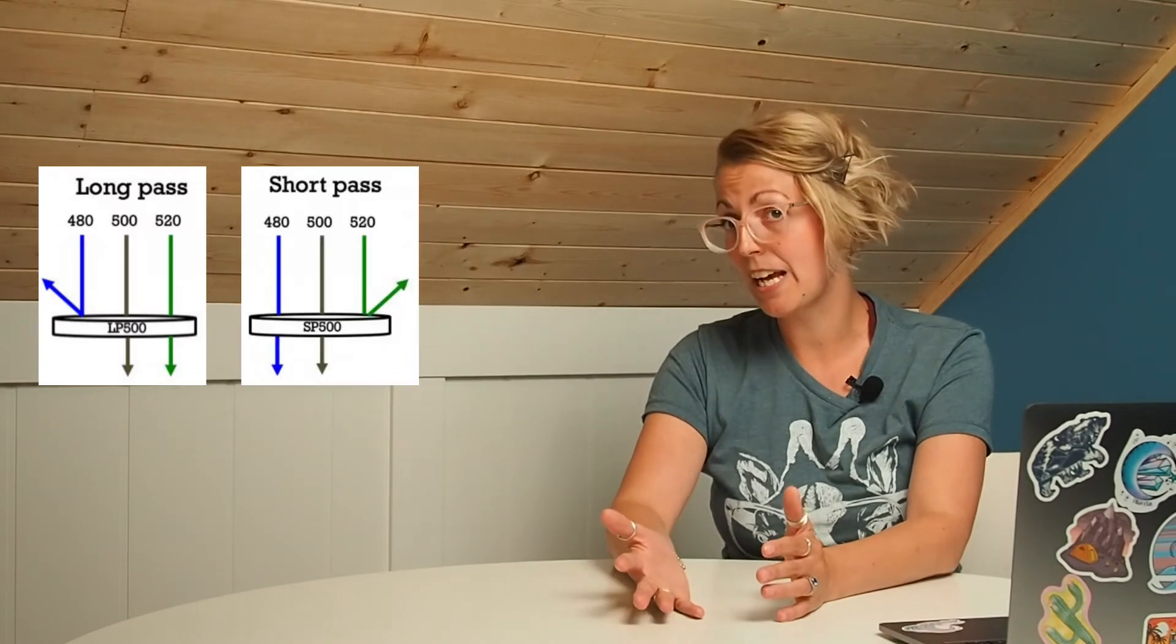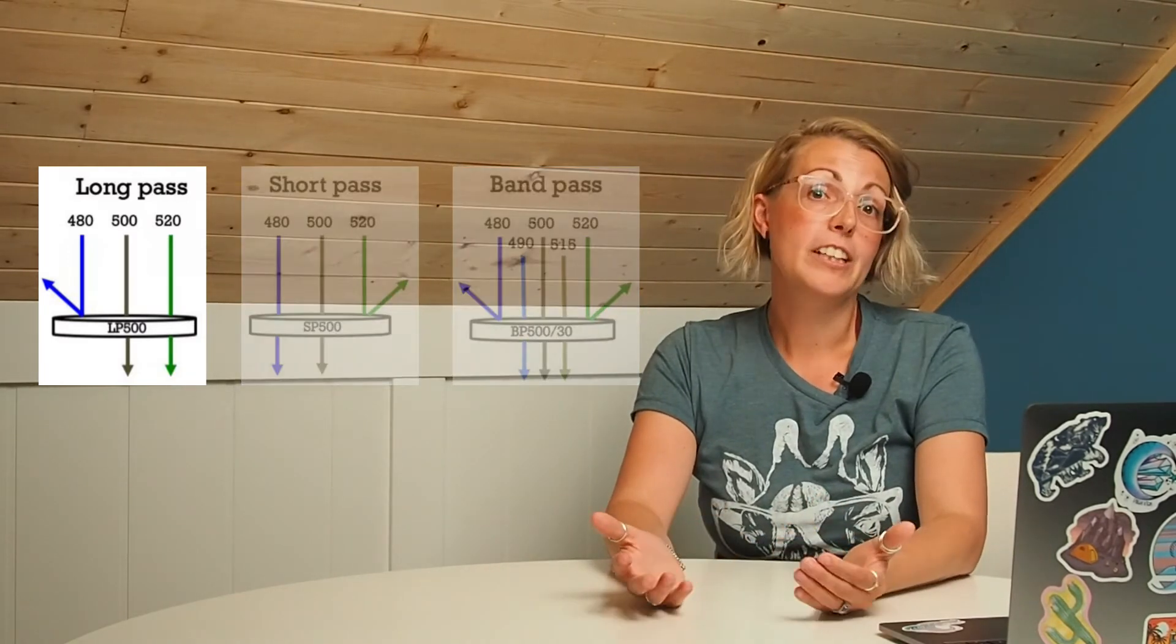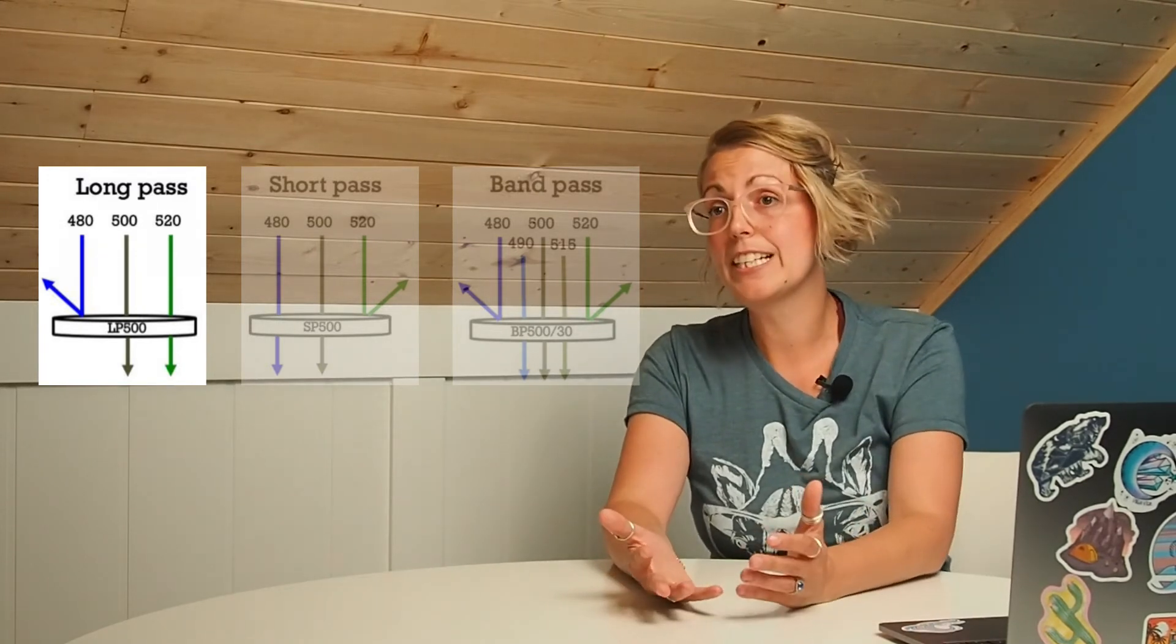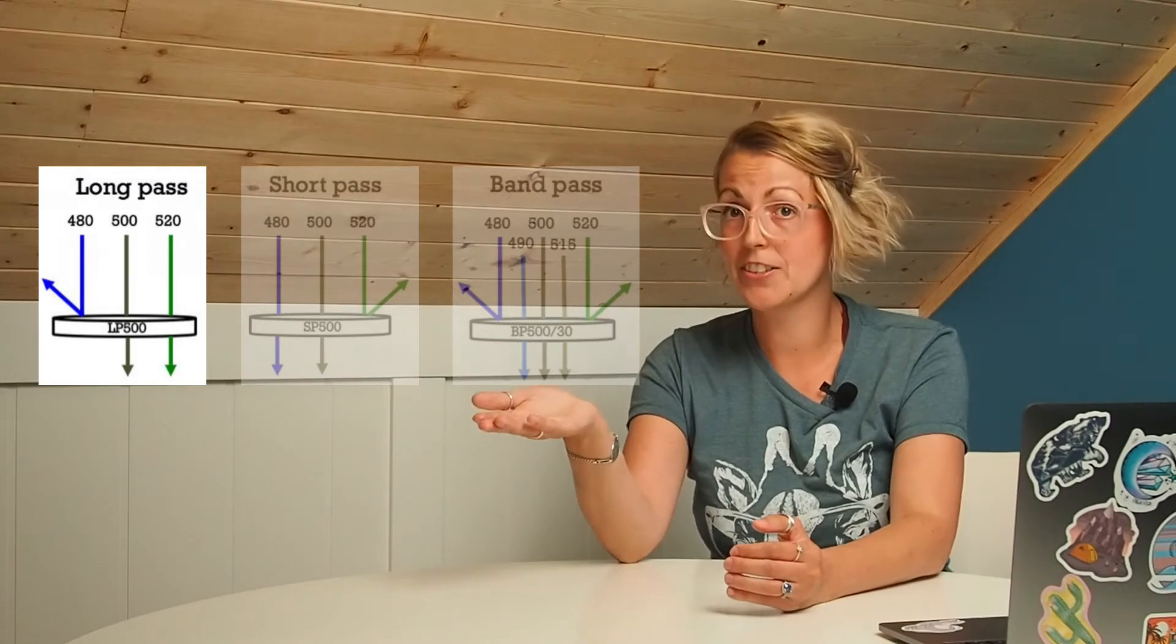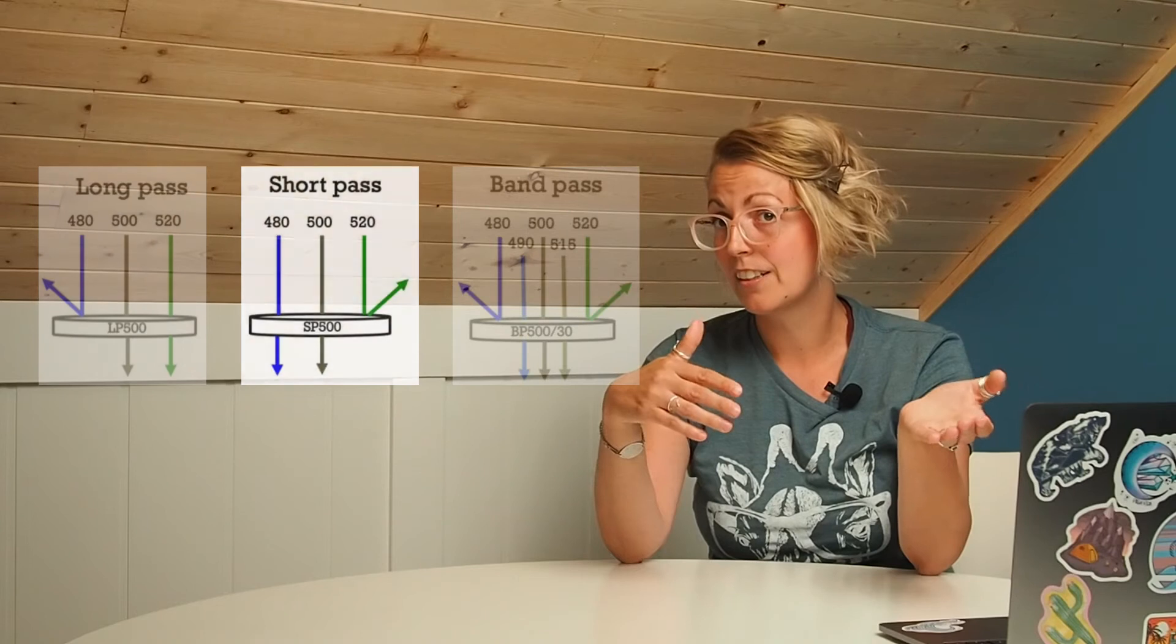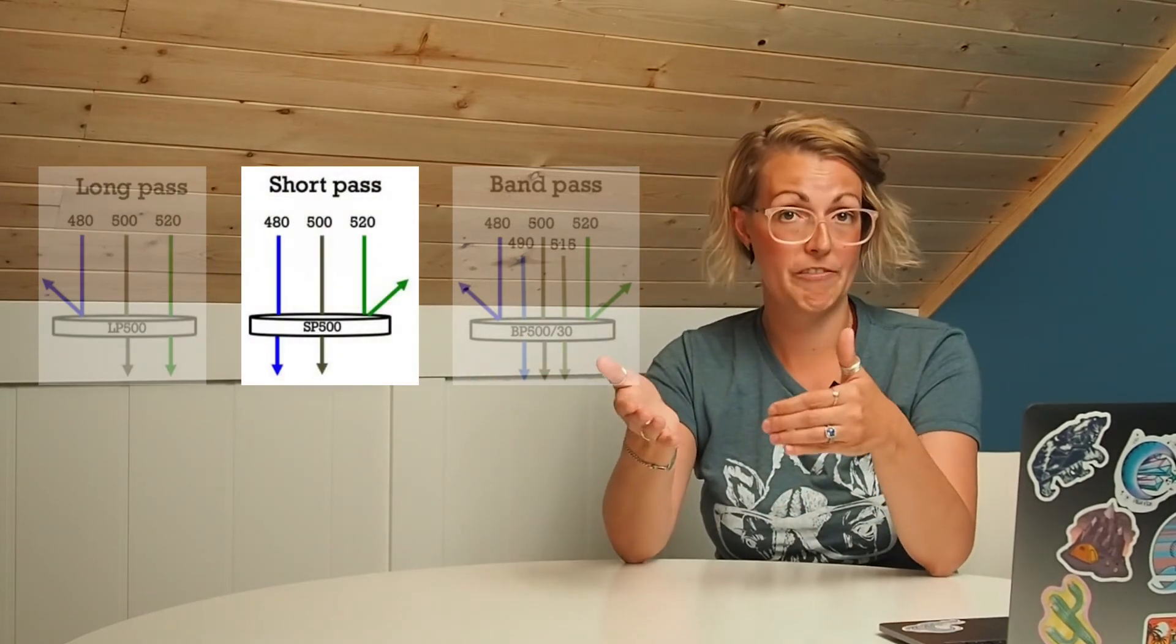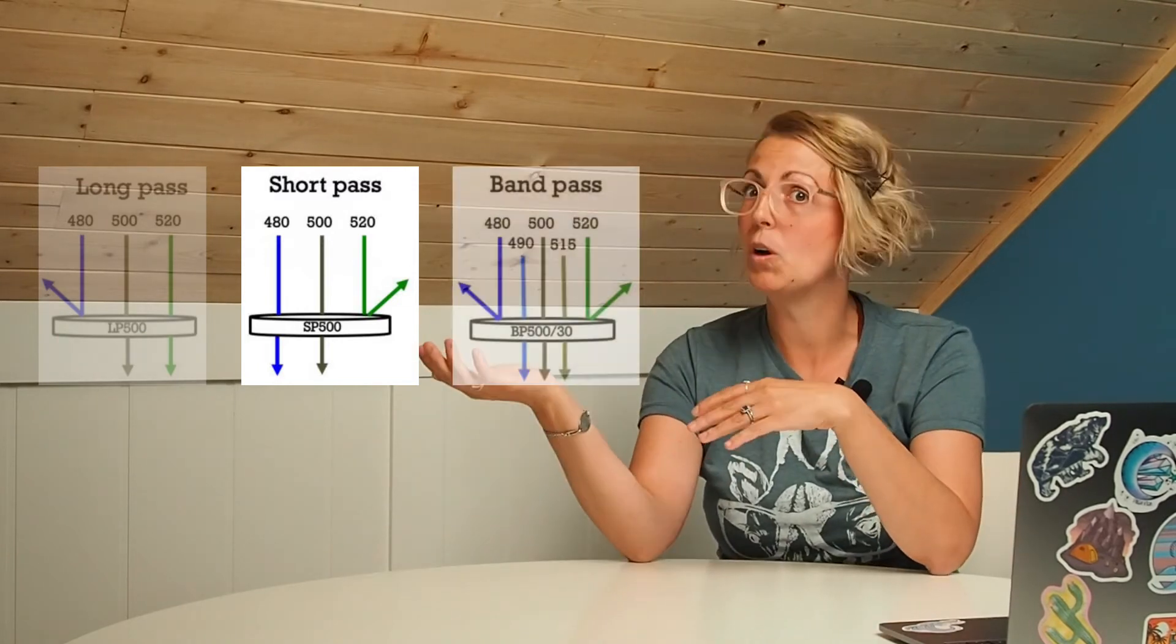Downstream of the lasers you then have a series of filters that break up the light and send it on to detectors. Now these filters come in three main flavors: the long pass filter, the short pass filter, and the band pass filter. If we look at the long pass filter and say we have a long pass 500 essentially what this means is any light longer than 500 nanometers will pass through, any light shorter will not. A short pass is the opposite. So a short pass 500, anything shorter than 500 will pass through, anything longer will not.